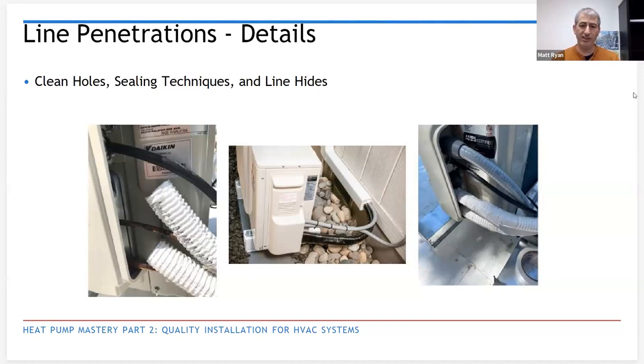Center photo there, you can see a pretty good example of a line set well wrapped and protected. It's a great job at keeping the UV off of it. And then another example there on the right of just a good clean one, insulated all the way to the connection point there. Also on that center picture, you can see where they come out of that line hide. They did a good job sealing that end off there, making sure nothing's going to go in or out of there.